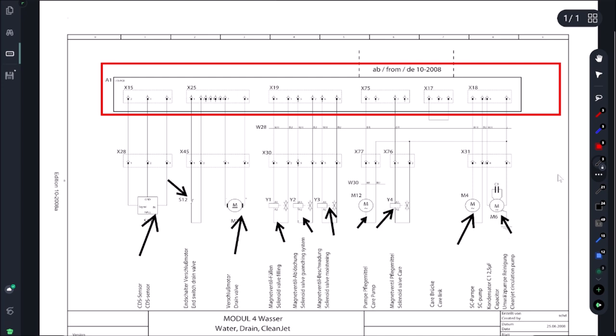I'm just going to go to the usual suspects - the solenoids and this pump here and these two pumps. So the clean jet pump as well as the SC pump, which is your emptying pump. I'm going to disconnect all these, we're going to isolate and plug things in one at a time until we find out what's popping that fuse.